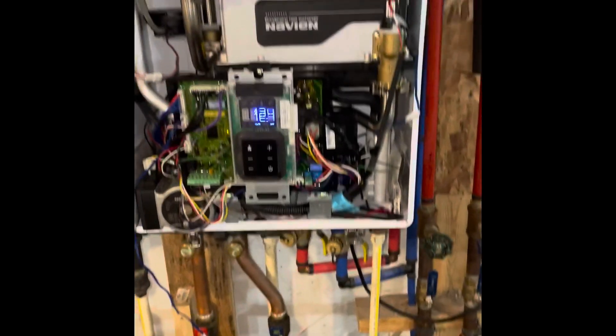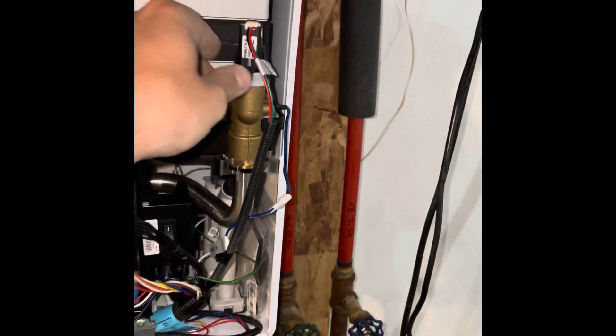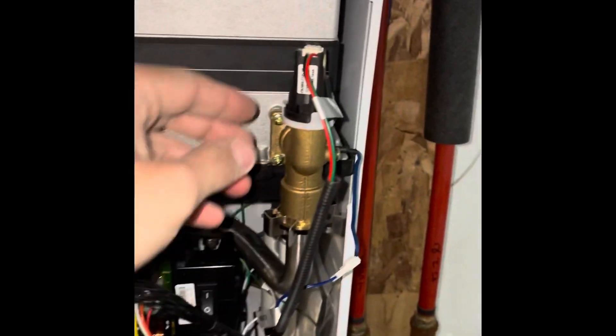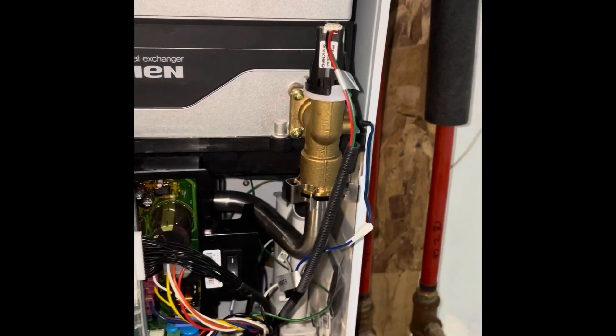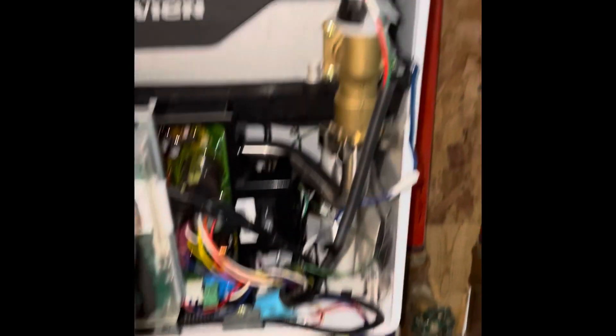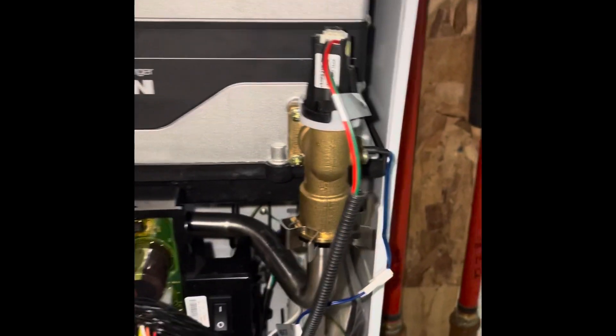I'm not going to say how to isolate the water coming out of this pressure sensor because I probably did it the incorrect way. But if you take this off and you do not isolate the water pressure sensor, a lot of water is going to come flying out at very high pressure. You can look up a video on isolating it, or just go ahead and unscrew it, let the water fly out, and quickly screw the new one on — I've seen people do that before.